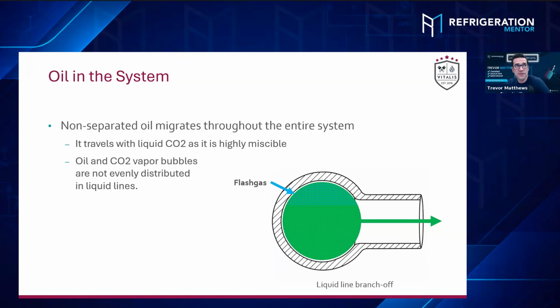So why wasn't this done for HFC, Jonas? So the difference between HFC liquid and CO₂ liquid is basically HFC is not a transcritical system. So you get the subcooled HFC liquid coming back from the condenser, and it's warmer than the environment, right? If you condense at 30, 40 degrees C, your liquid will always subcool with the ambient condition because the ambient with HFC liquid is always colder. So it cools down, it produces more subcooling, and it will not create a lot of flash gas.